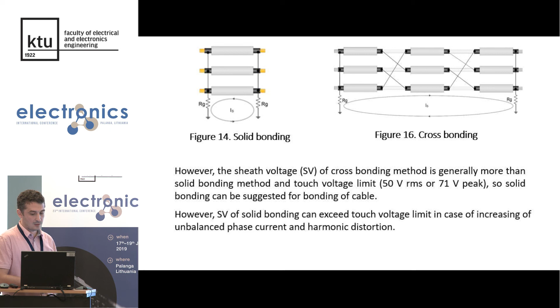However, SV of solid bonding can exceed touch voltage limits in case of increase of unbalanced phase current and harmonic distortion. When SSB is used, SV does not exceed touch voltage limit for human. SSB is shown in this figure. However, if length of cable line exceeds 1 kilometer, harmonic distortion rate and SV increase due to cable capacitance. So cable termination fault occurs in cable line. Thus the modified SSB, MSSB, is developed for long high voltage underground cable line under high voltage distortion case.